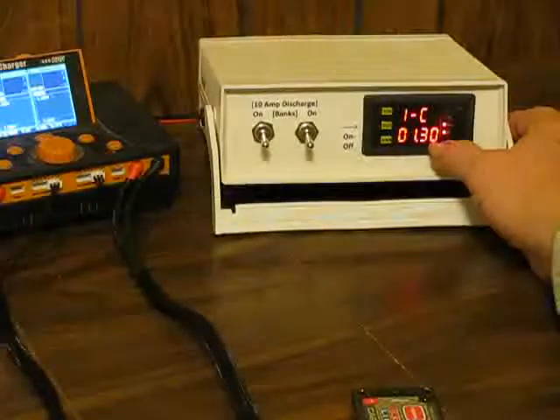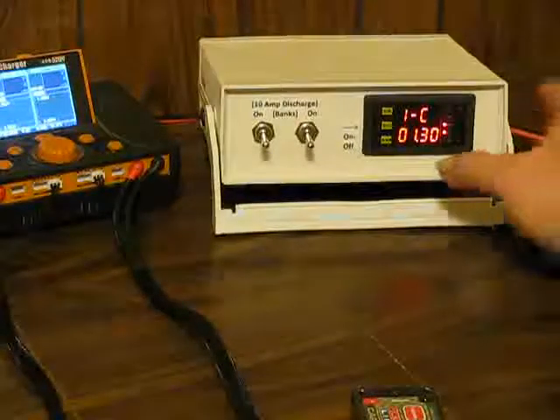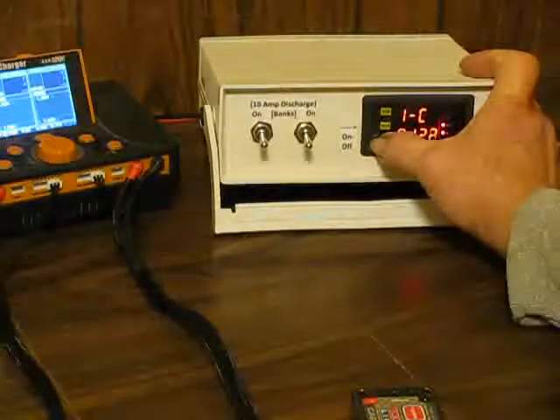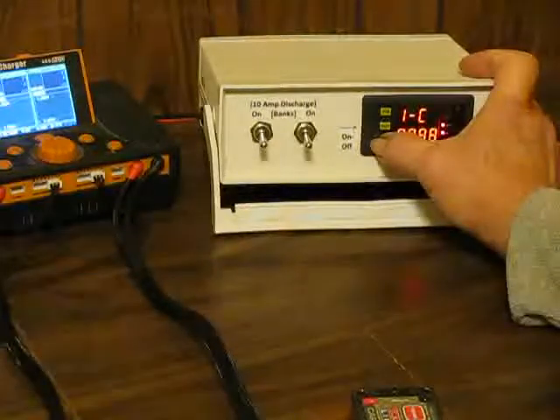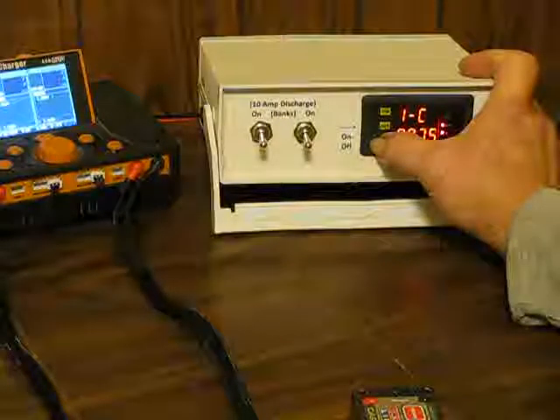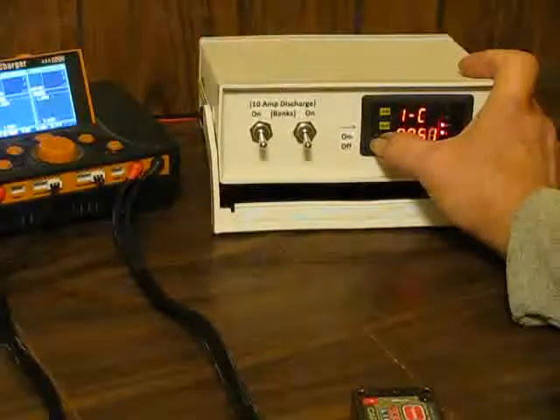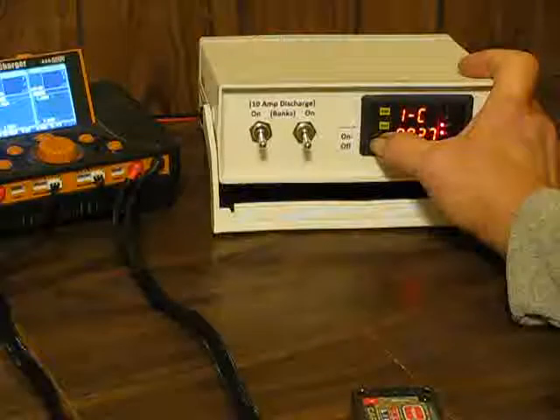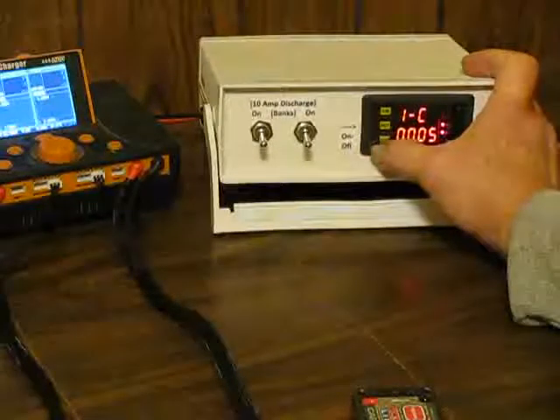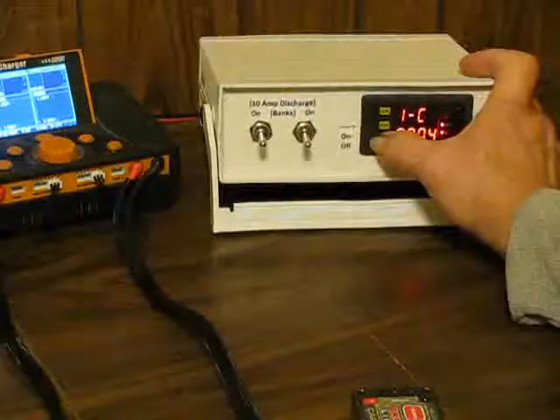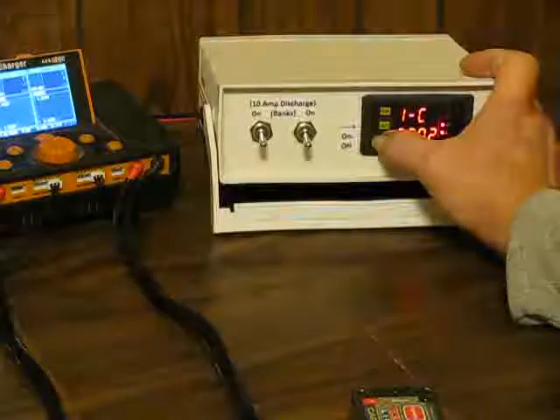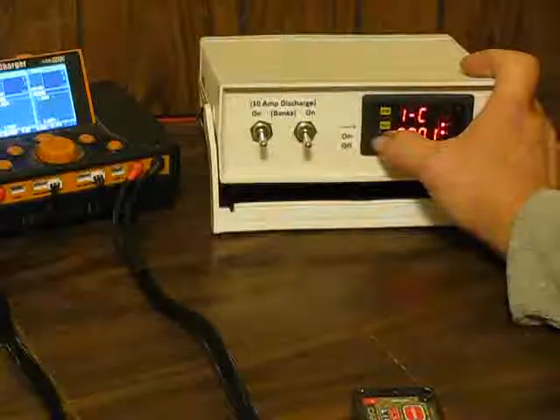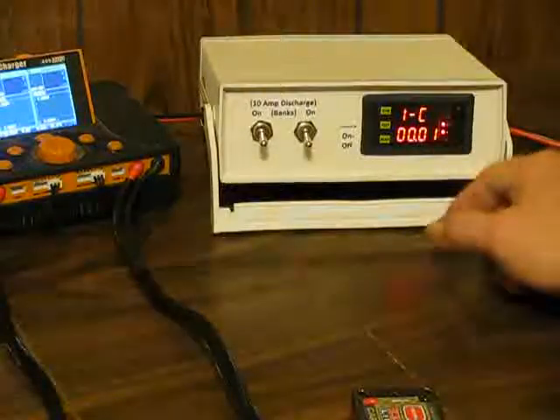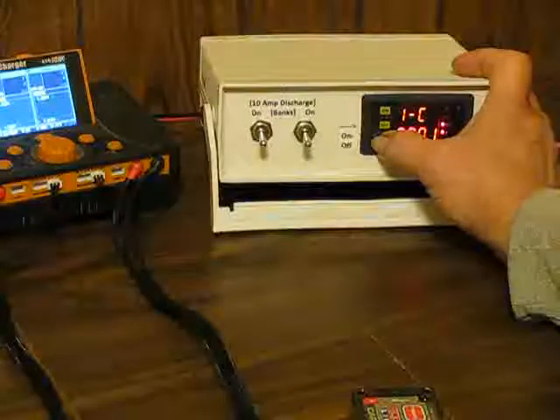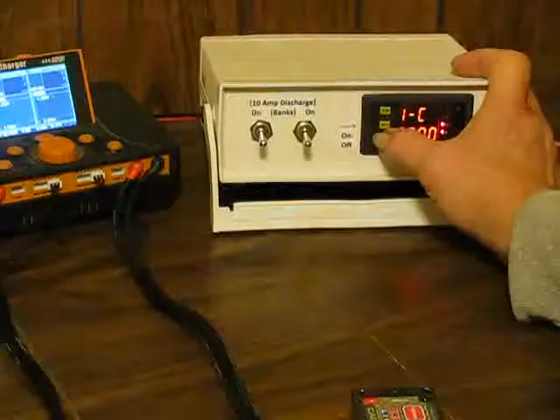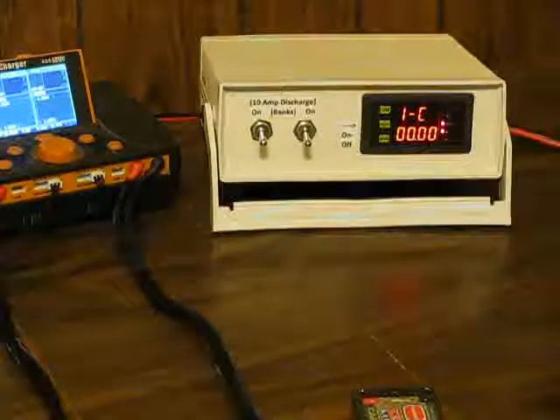This is your amp rating. It's showing 1.3 amps, which is way too high, so we'll hold down the lower button and creep it down the same way, down to 0, or actually 0.01 — 0.5, 0.4, 0.3, 0.2, 0.1. Go just a little bit more. Clicking the button, it'll take about 5 clicks to go down a hundredth, to 0.01. Get it down to 0, then go about 3, 4, 5 more clicks, and that should be pretty close.